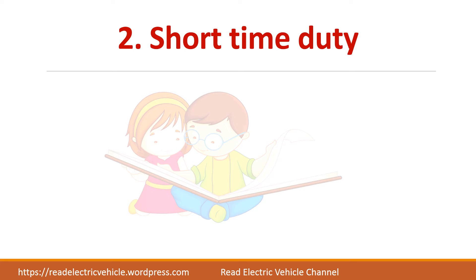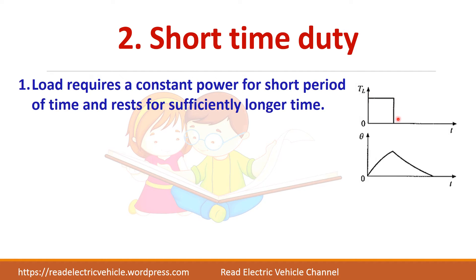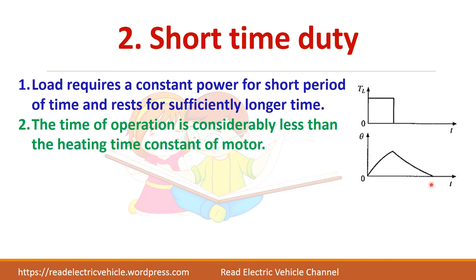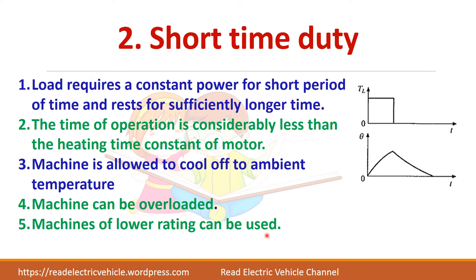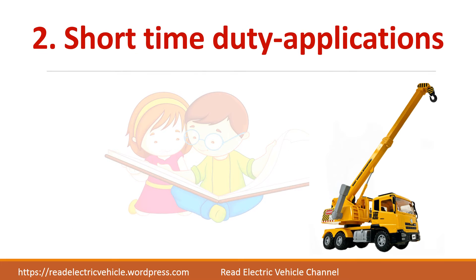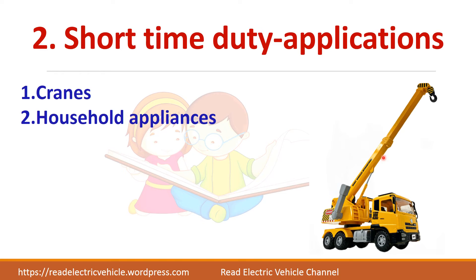Next is short time duty. Here, the load will be available only for a short time and after that, the motor will go to rest position. In that case, the temperature increases and there is sufficient time to cool down. The machine is allowed to cool to ambient temperature. So in this case, you can overload the machine because you are getting sufficient time to cool down. The machine can be easily overloaded, and a machine of lower rating can be used for such applications. The best example is cranes, as they are used only for a particular period, not at all times. Household appliances also come under short time duty.